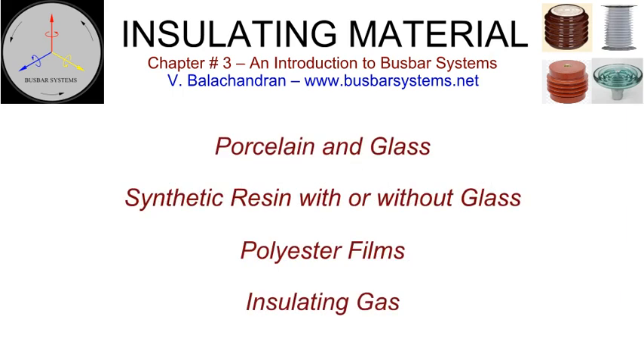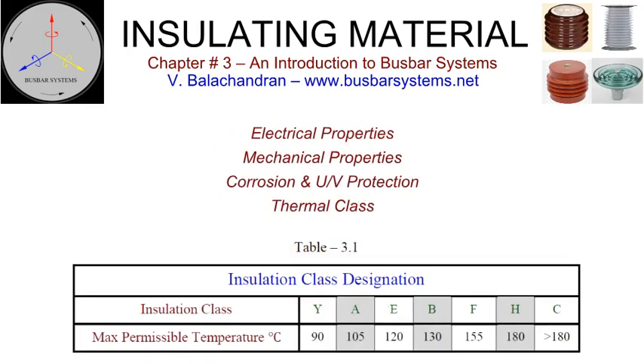The insulating material in busbar systems can be broadly classified as under: porcelain and glass, synthetic resin with or without glass, polyester films, insulating gas. The following major properties are to be considered when selecting an insulation system. Electrical properties. Good electrical properties are the most important criteria for insulating material. Among others, these include high breakdown voltage, low loss angle, tan delta, and high surface resistivity. Mechanical properties. Good mechanical properties of insulating material will result in a compact insulator. Among others, these include a combination of high tensile, compression, cantilever, torsional, cross-breaking and impact strength, and moldability.